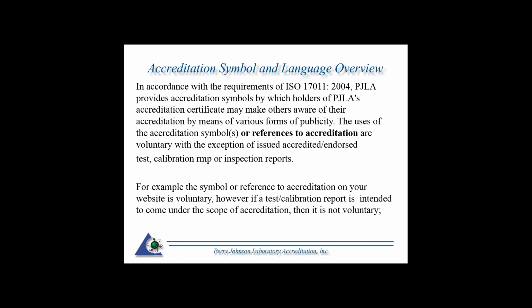That's up to you if you want to use it there or not. Your marketing materials, things like that. When you reference it, that does have to be referenced in a certain manner, which we'll look at here shortly. However, if a test or calibration report is intended to come under the scope of accreditation, then it is not voluntary. So in other words, if you have a customer and they're requesting a test or calibration to be done under your scope of accreditation, then it is not voluntary. You have to either use the logo or reference accreditation in the appropriate manner.